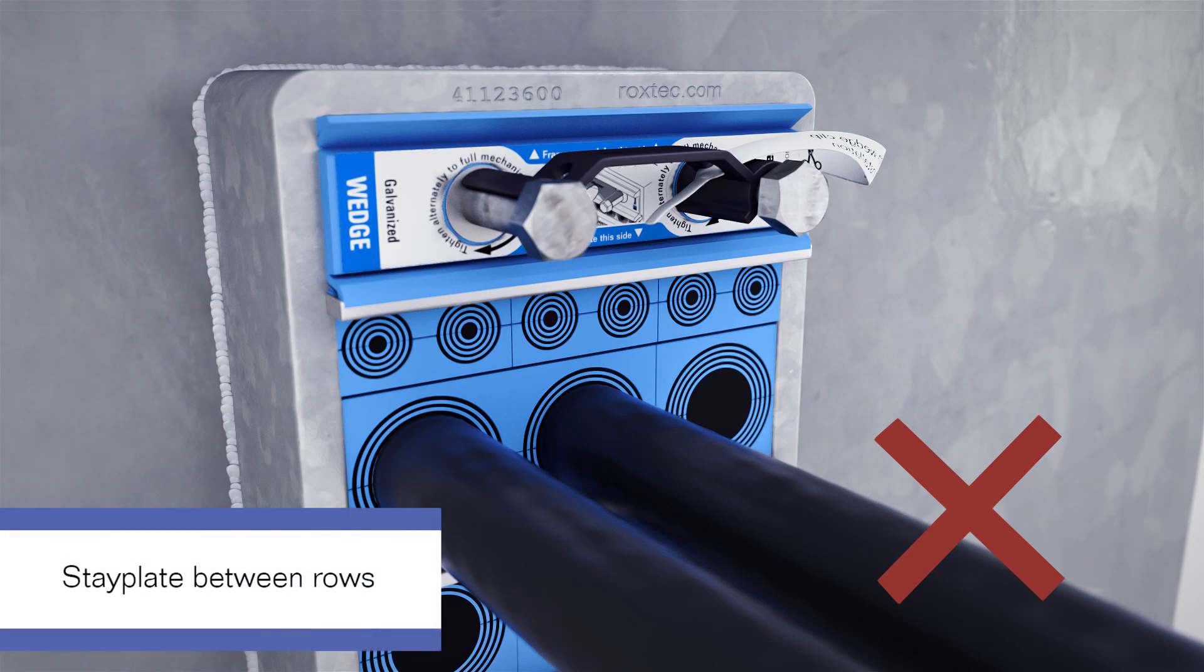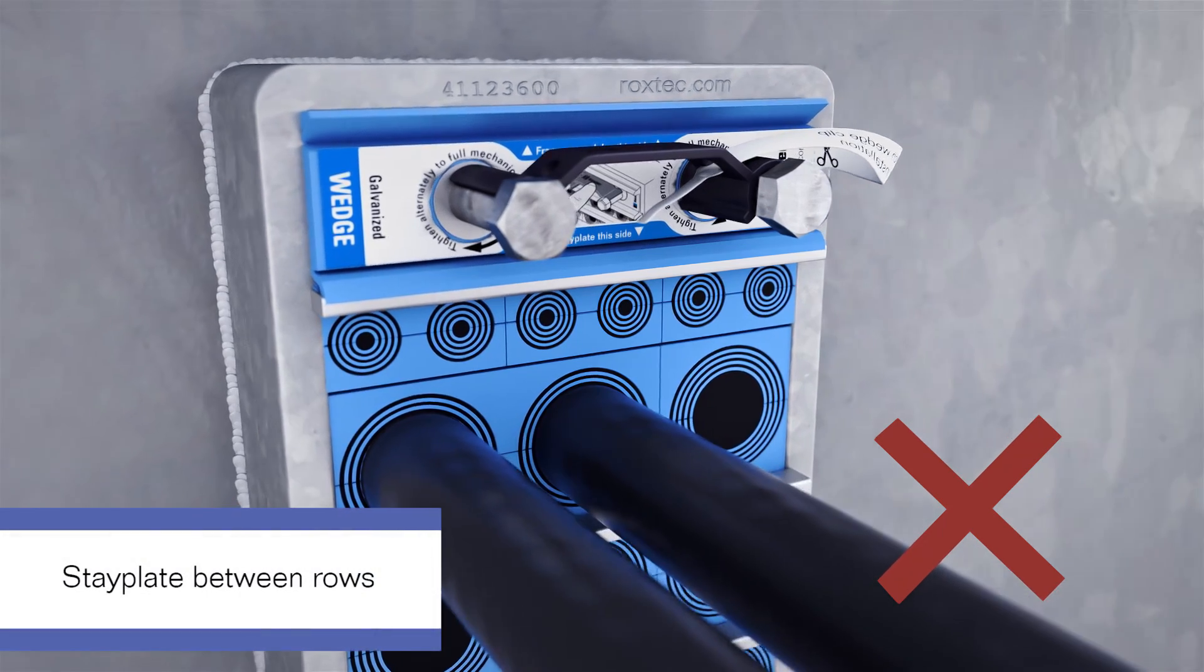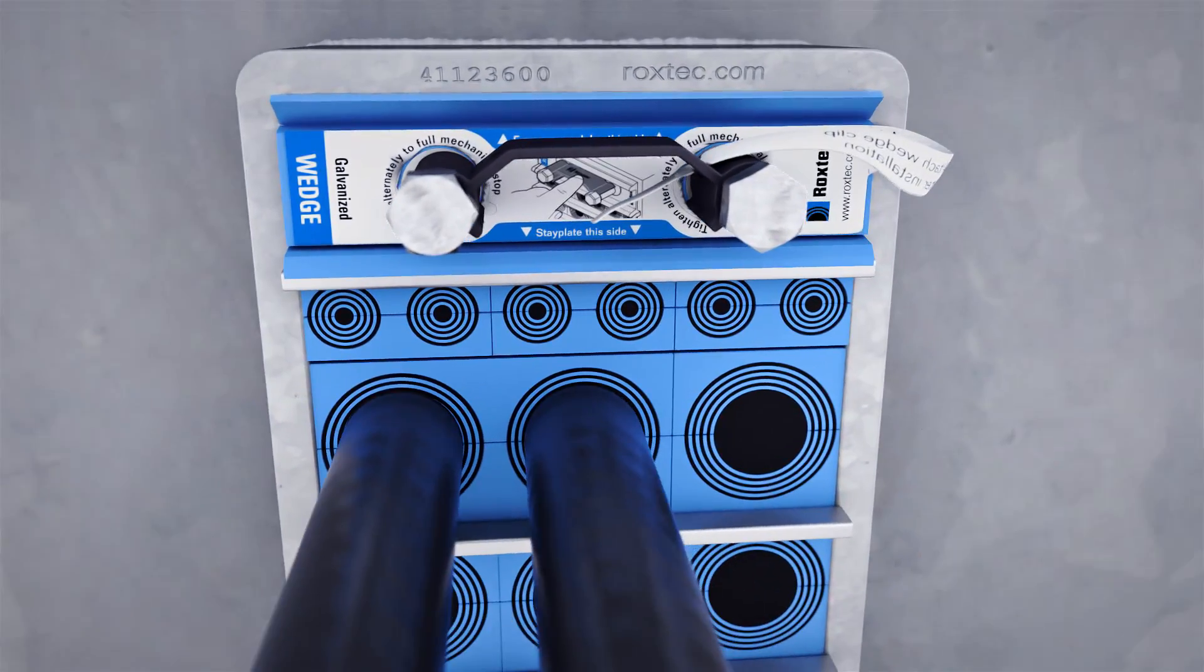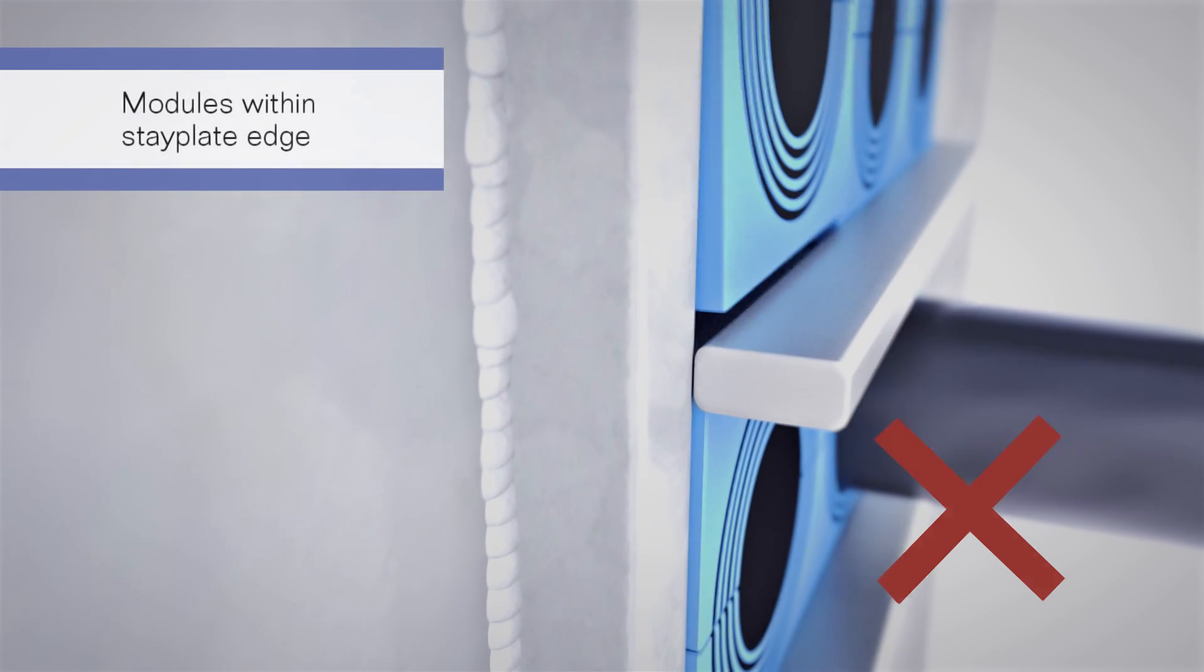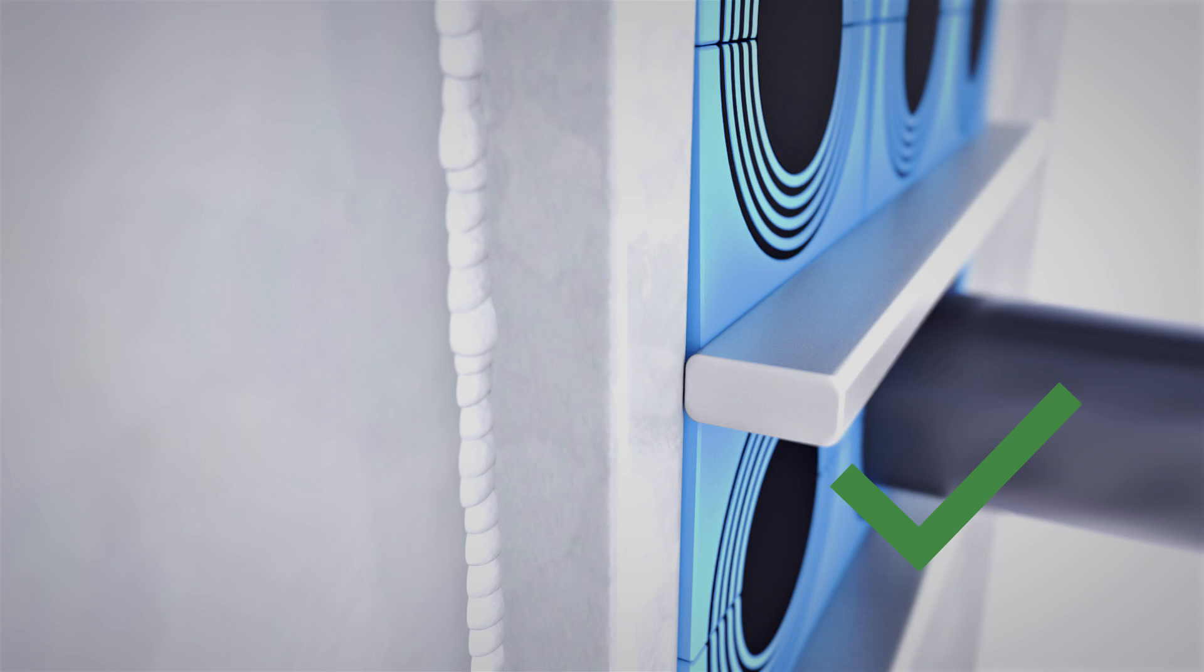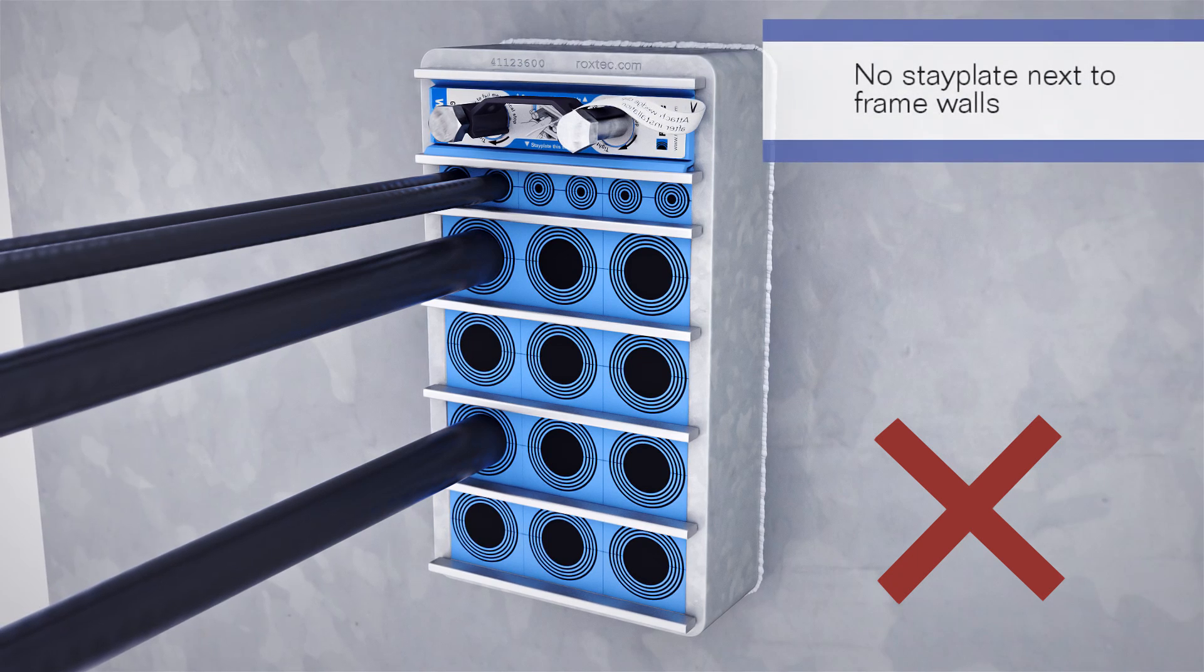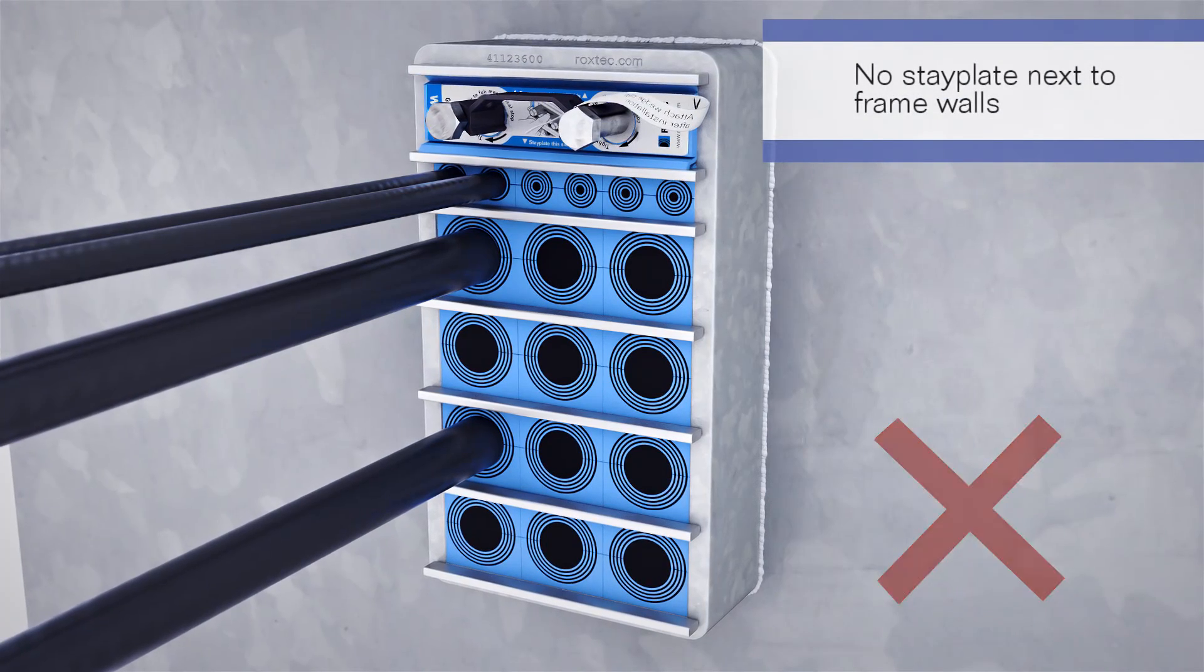Check that each consecutive row of modules is divided by a stay plate. Check that all modules are secured within the stop flanges of the stay plate. Verify that there is no stay plate installed next to the frame walls.